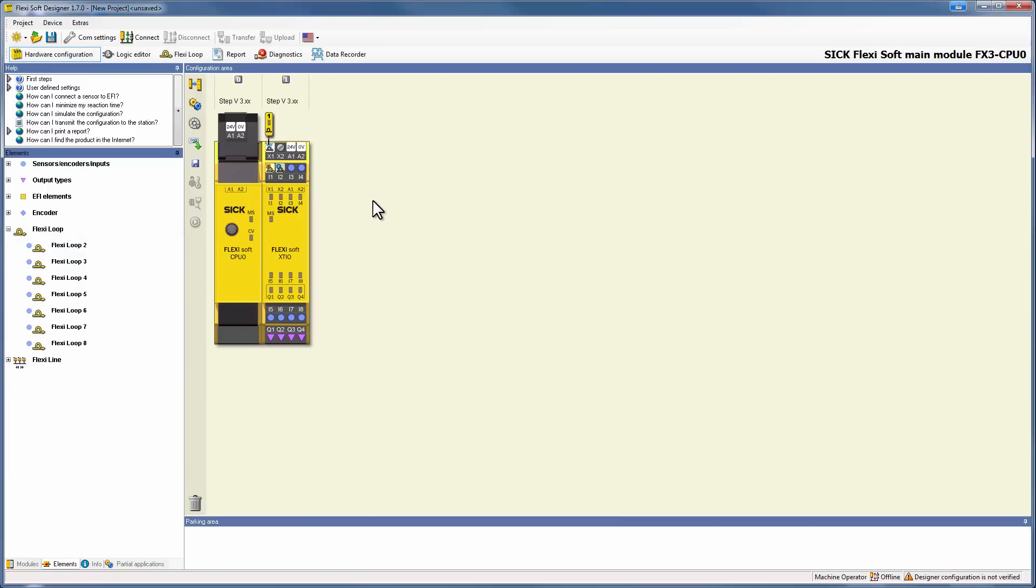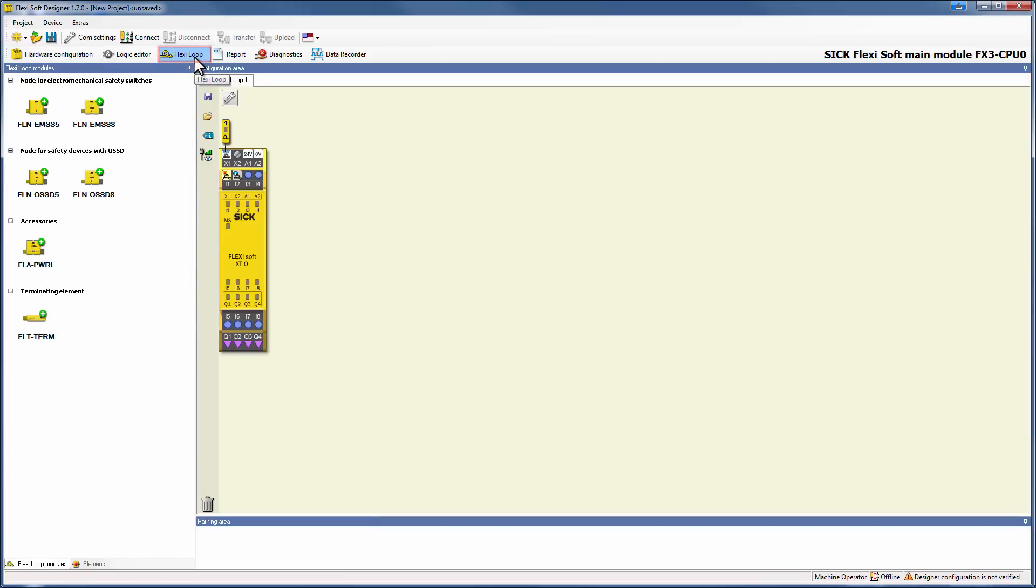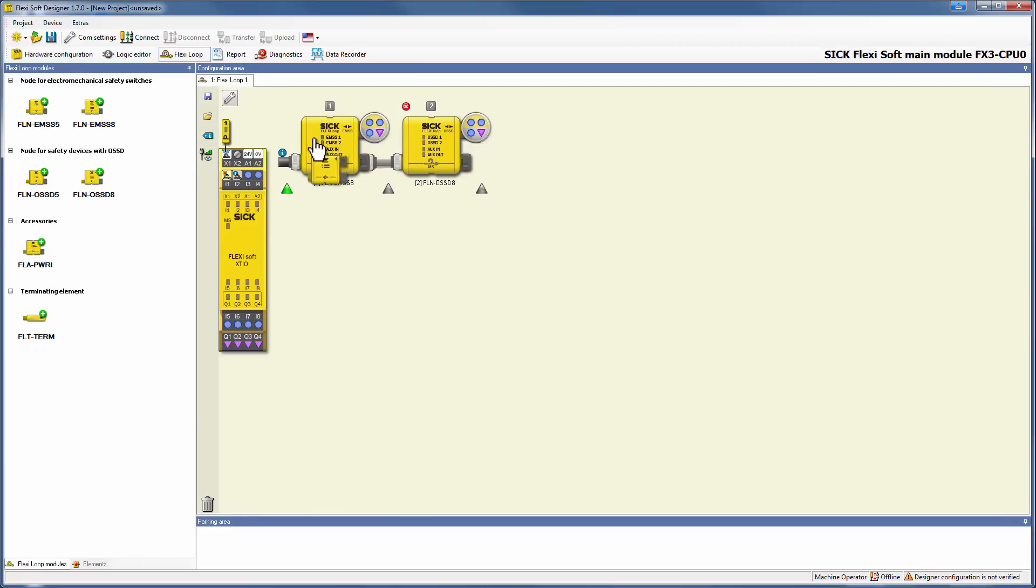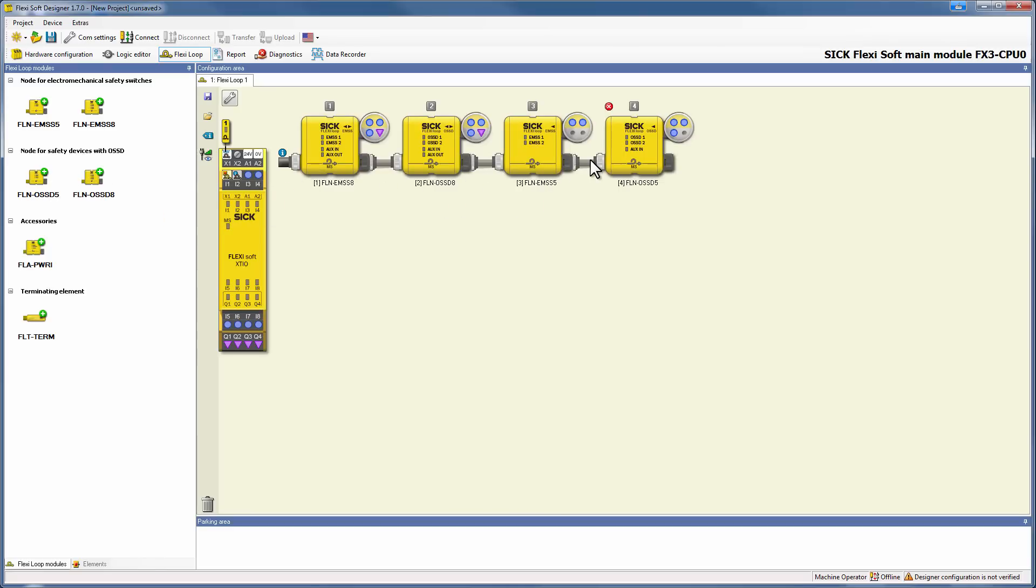Now we are going to configure the nodes. Therefore we switch to the FlexiLoop area. Here we start adding the nodes we need for our configuration, of course via drag and drop. I am going to start with one node of every type. After we successfully added all our nodes, we need to end the cascade with the terminating element.